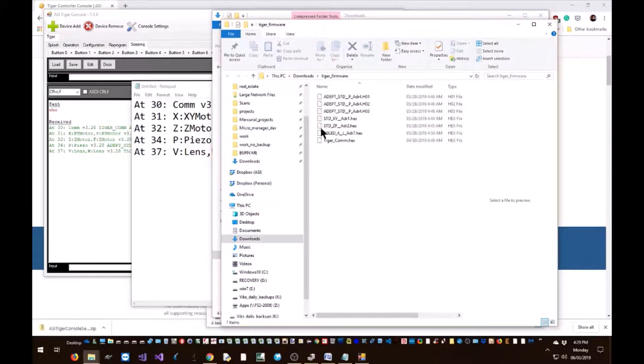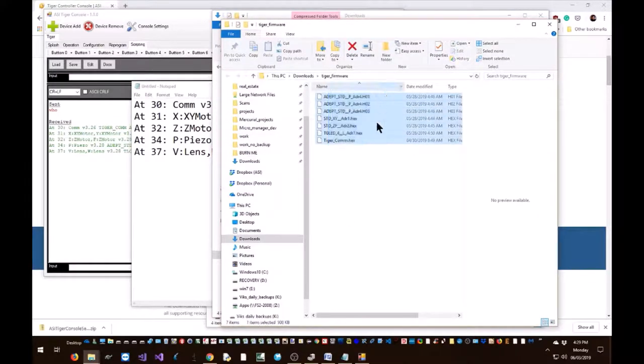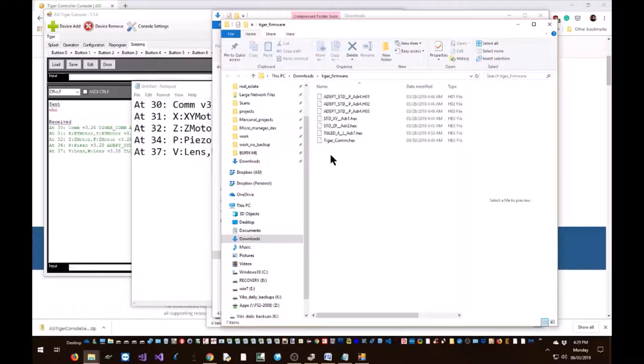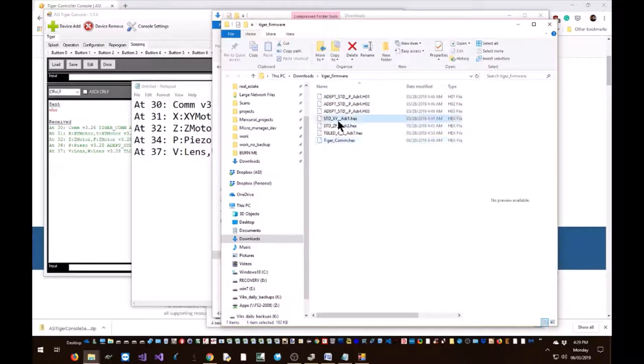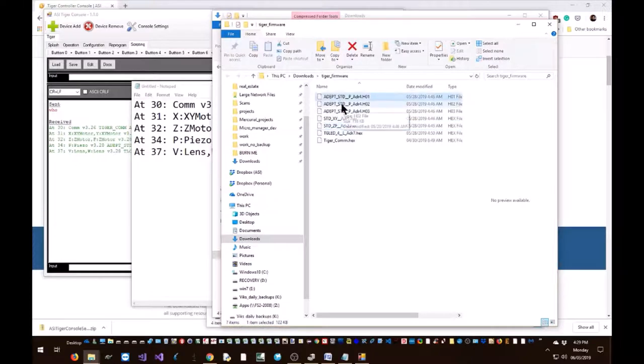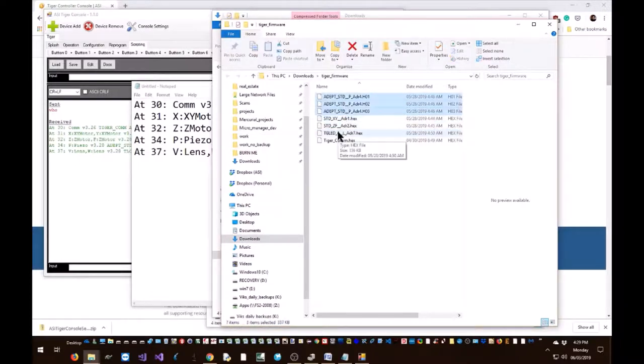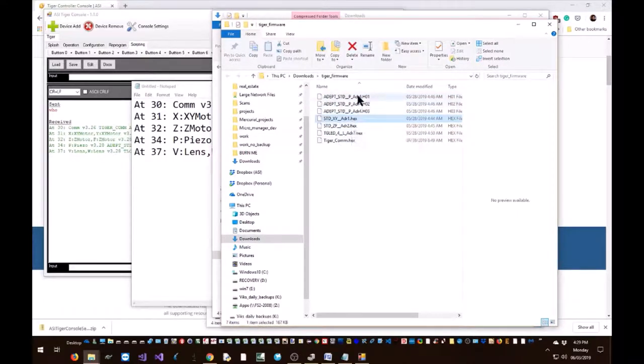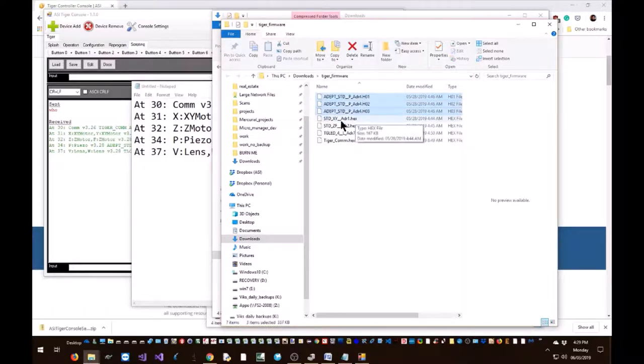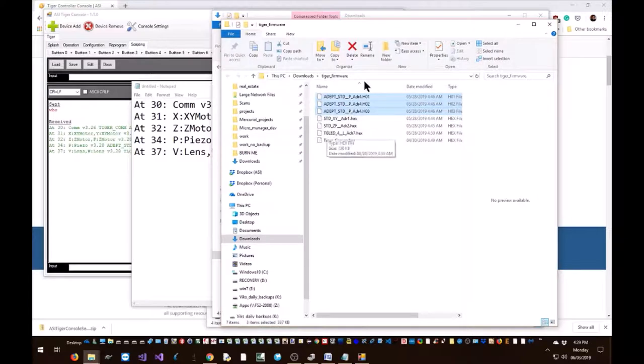And then you can see all the firmware listed. Since our Tiger controller has five cards in it and each card has its own microcontroller, there are five sets of firmware here. There's the firmware for the COM card, the firmware for the standard XY card, the firmware for the ZF card, and the firmware for the LED card. Sometimes the firmware is just a single file called a hex file, and sometimes it's split up into three files. They are one and the same; it just depends on the size of the firmware.